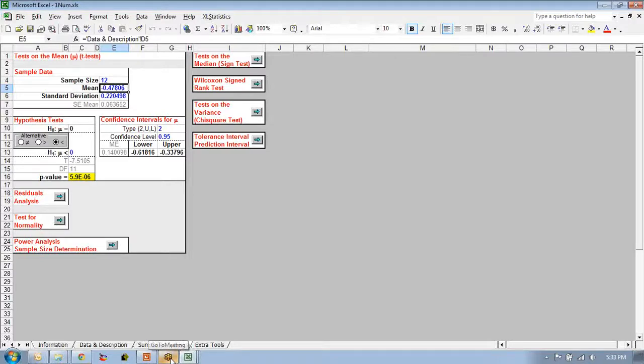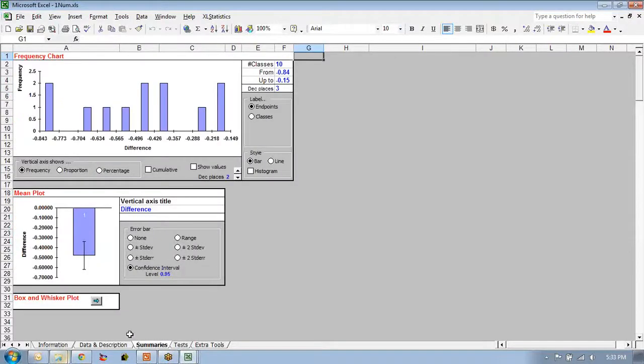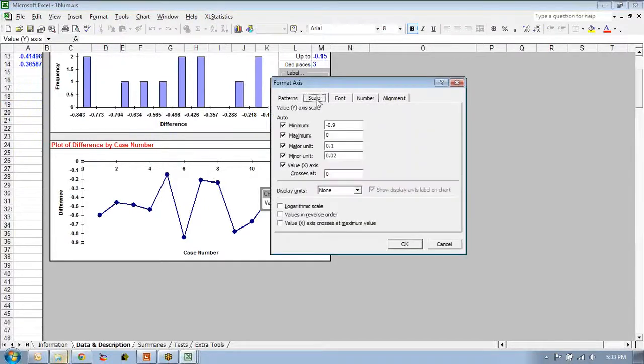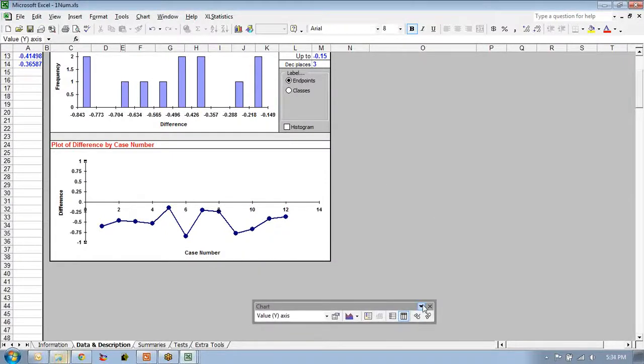That's it for the accuracy study — there's not much more to it. One other thing you could look at is the data over time, and you can see the bias looks pretty consistent — it's bouncing around minus a half rather than around zero. This would be an example where this flow meter needs to be sent back and calibrated. If you find a bias in a people measurement system, that could mean that there's training needed or that some definitions are off.